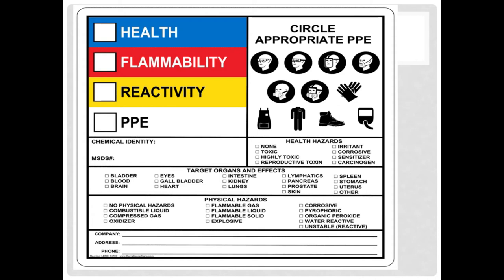The flammability and reactivity chart — the NFPA diamond — is rated 1 to 4 and seen on trucks and containers. Blue shows health hazard rated 0 to 4 (0 = no hazard, 4 = very high). Red shows flammability: a rating of 1–2 means less flammable, 3–4 means highly flammable. Yellow shows reactivity, and white shows personal protective equipment requirements. MSDS (Material Safety Data Sheets) include CAS number, material ingredients, purity, health hazards, environmental hazards, fire hazards, and extinguishing media.